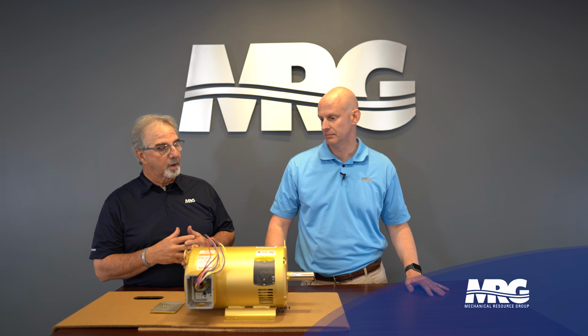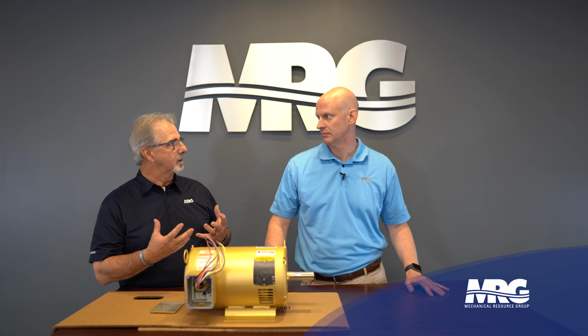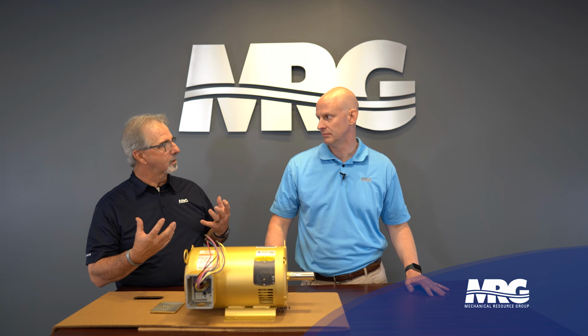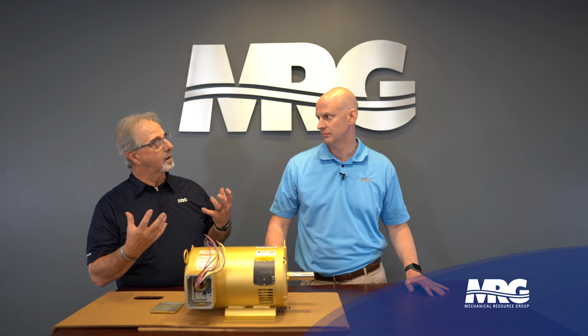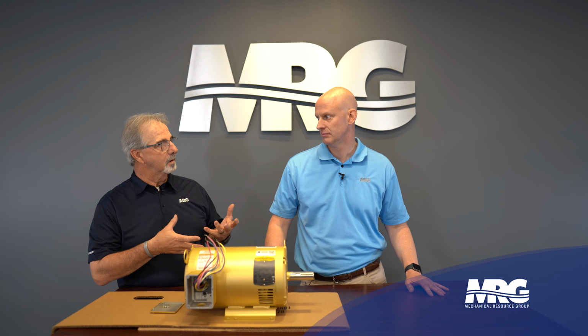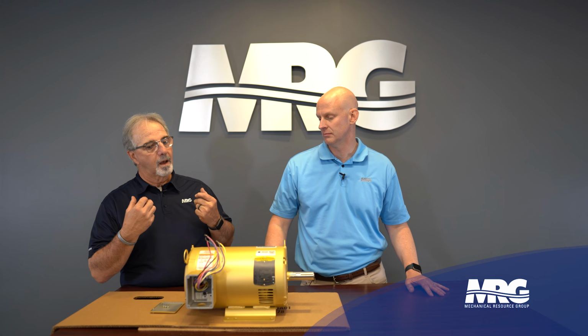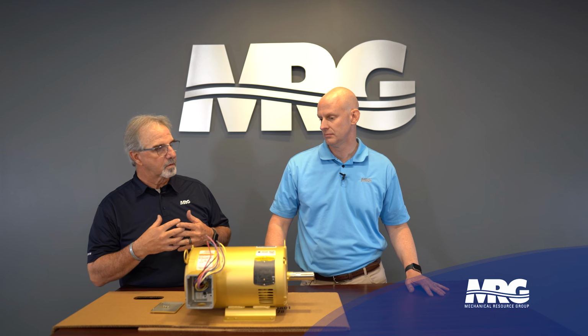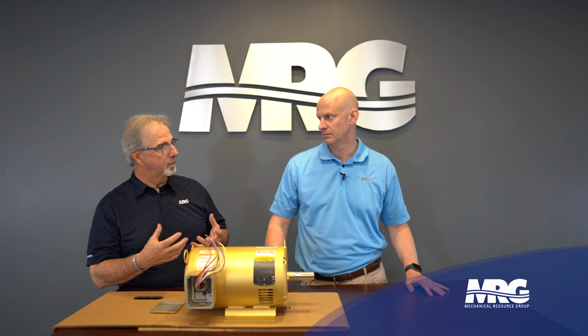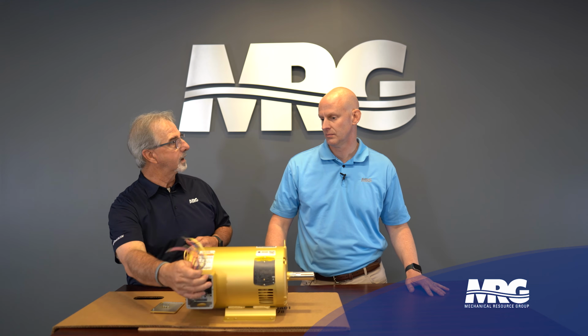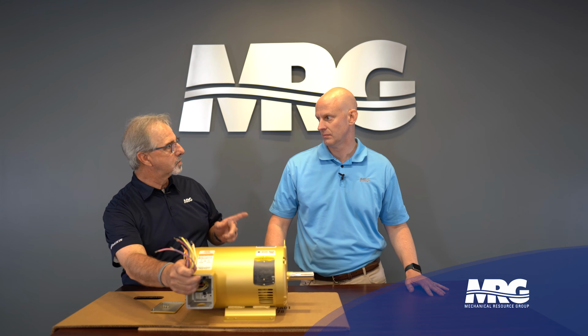Because what we're going to talk about today is electromechanical, and electromechanical is kind of an antiquated technology, but it's what we had before. But we still see it. Our service techs still see it, and so we all have to be on the same page on how a motor is to be connected. Now, this particular motor, 9-lead motors, are not suitable for reduced voltage starting. So let's go back. Electromechanical was the old school way of doing a soft start.